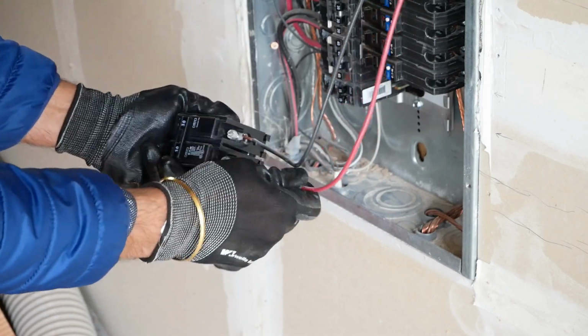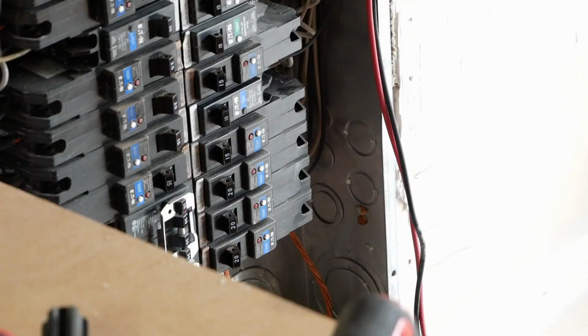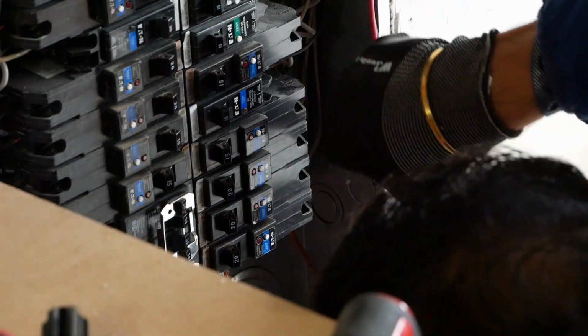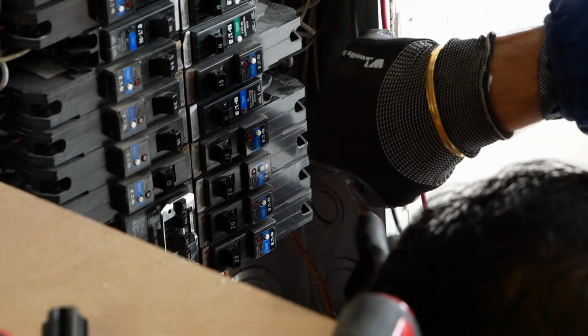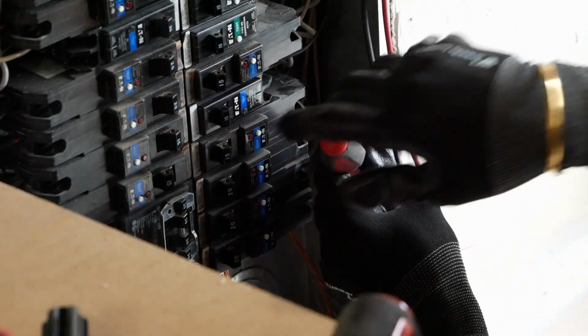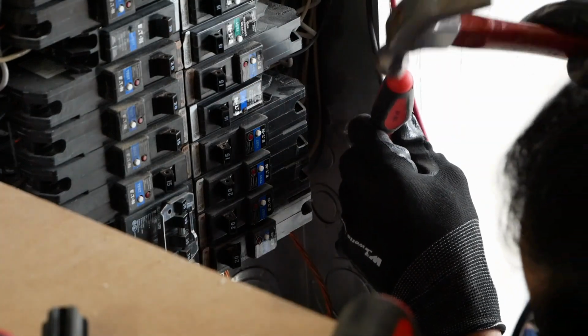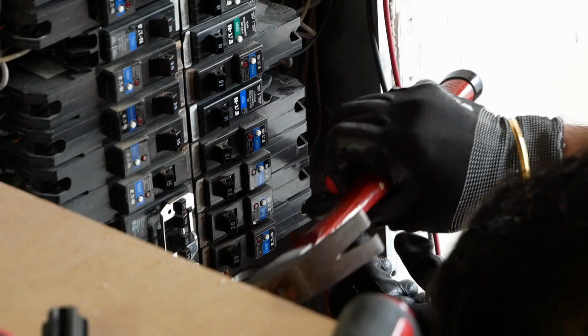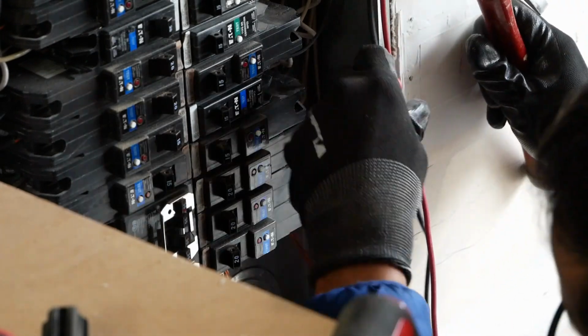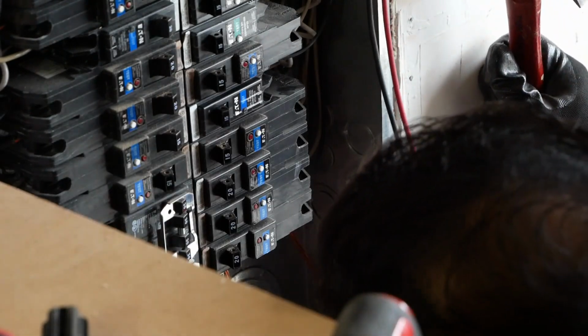As we explained, we would be removing the dryer circuit breaker and replacing it with a quad 2-pole circuit breaker. Using a screwdriver, we took out the knockout plugs from the electrical panel and drilled a hole to fish the wire. This was a bit harder as the electrical panel was sitting right against a 2x4.